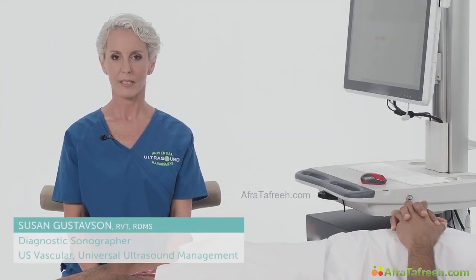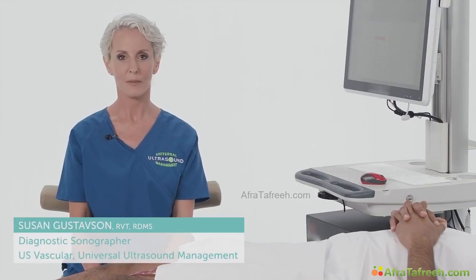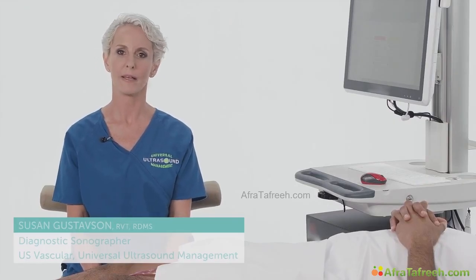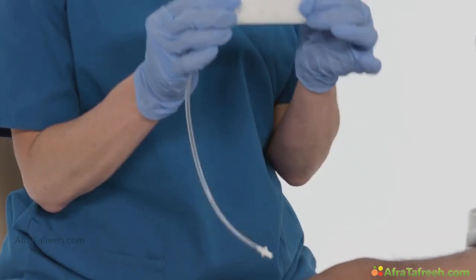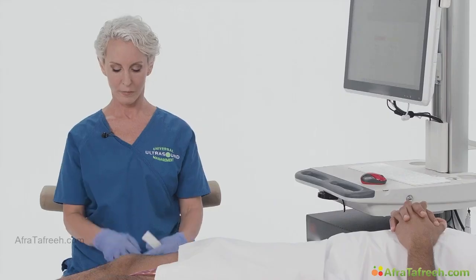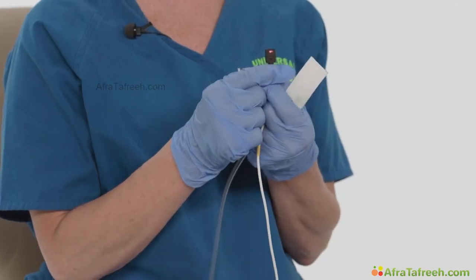Now I'd like to demonstrate how to obtain a digit pressure. When tibial artery pressures cannot be accurately obtained, such as in the case of medial calcinosis, ulceration, or bandages over the ankle, you can utilize the toe brachial index to determine if there's a decrease in the circulation to the lower extremity. For this method, we'll use a digit cuff, and we'll use photosensing technology.